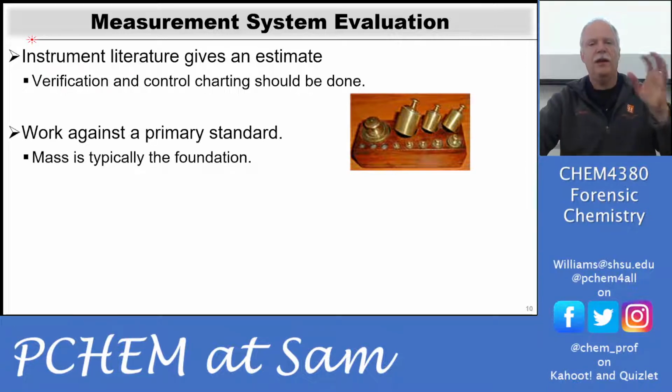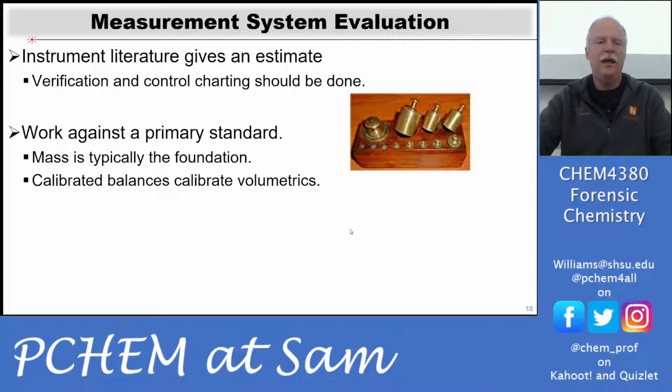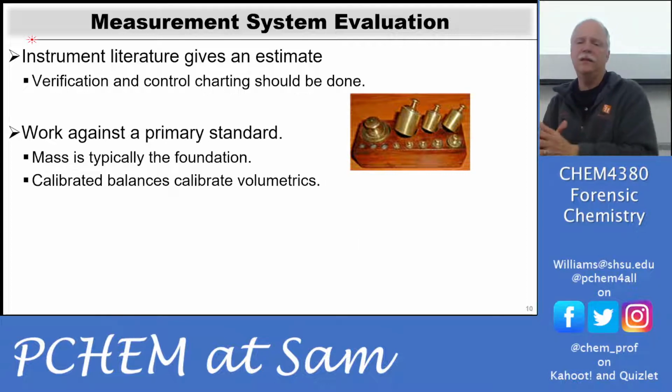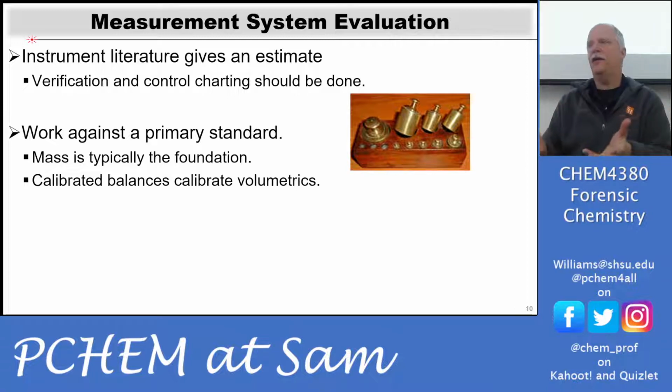But we want to consistently calibrate our instruments. And a lot of times these things work with balances. Mass is typically the foundation. And so we'll calibrate our balances, and we know that our balances are accurate. And then we'll use those balances to calibrate our pipettes. And so you may say, golly, to measure the mass of a 10 microliter drop, okay, do we really do that? Yes, we really do that.